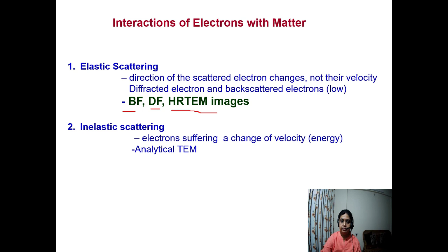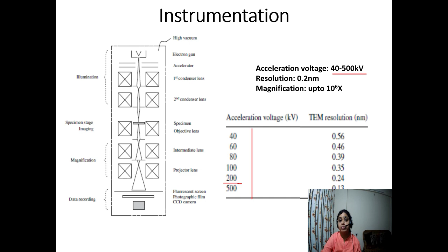So let's come to the instrumentation part. As in the SEM machine, there is an electron source, and then an illumination part, and then sample stage, imaging, then magnification, then the data recording part. Depending upon the acceleration voltage, the wavelength of the electron wave can be controlled, and hence resolution can be controlled. In a typical TEM machine, generally up to 200 kV is applied. However, in the higher end, it can vary from 40 to 500 kV. The best possible resolution with the TEM machine is 0.2 nanometer, and magnification up to 10 to the power 6 can be achieved.